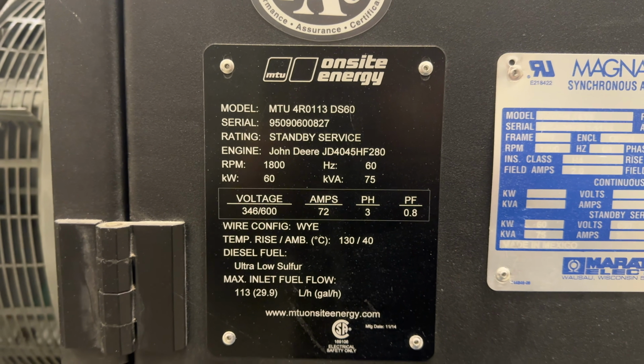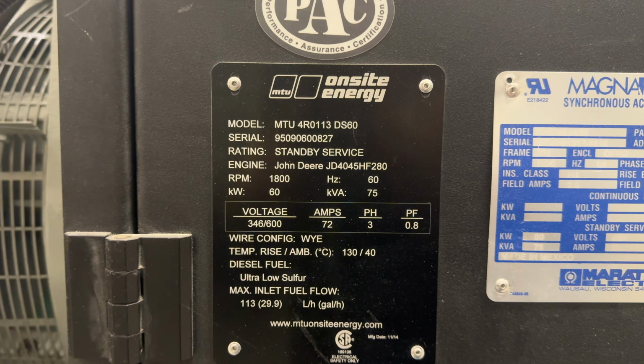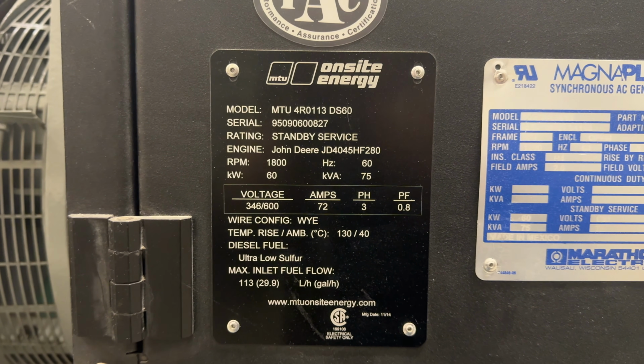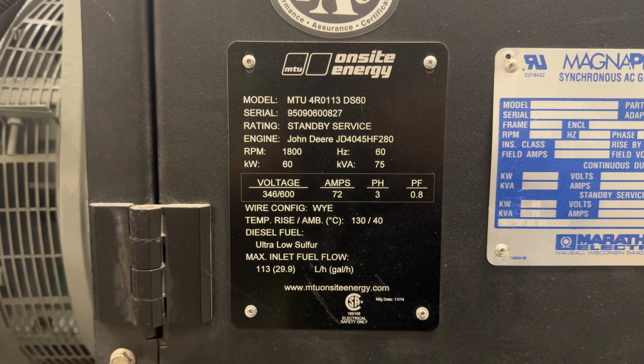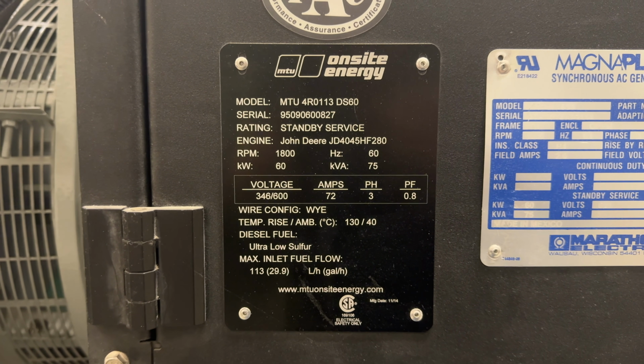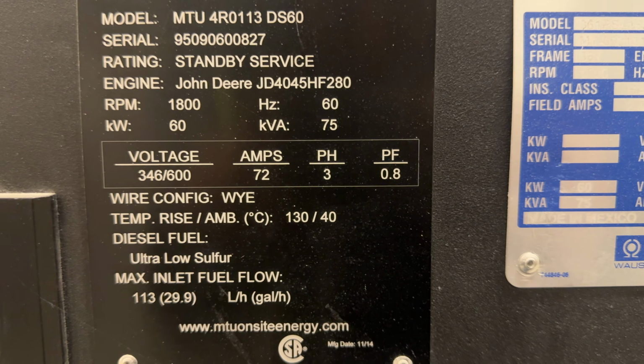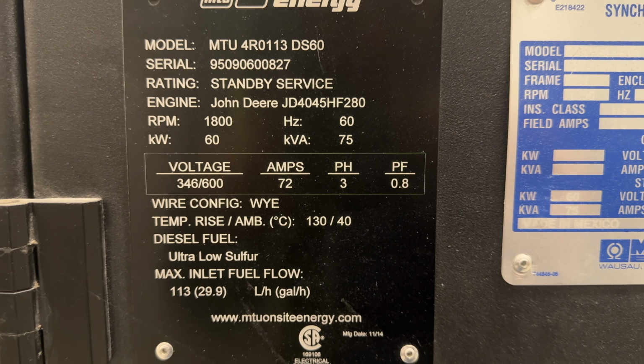You can see it's designed to run at 1800 RPM to hold 60 Hertz, and that is 60 kW or 75,000 volt amp. And that gives you 72 amps at 347/600.